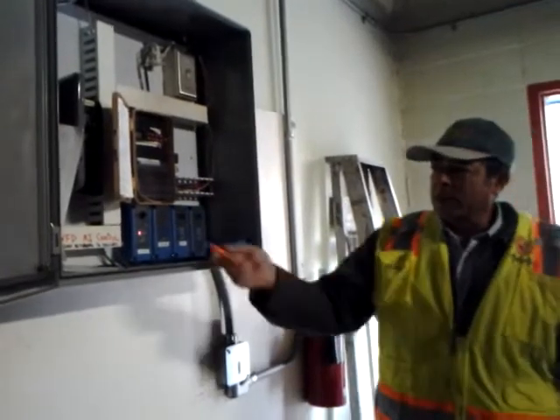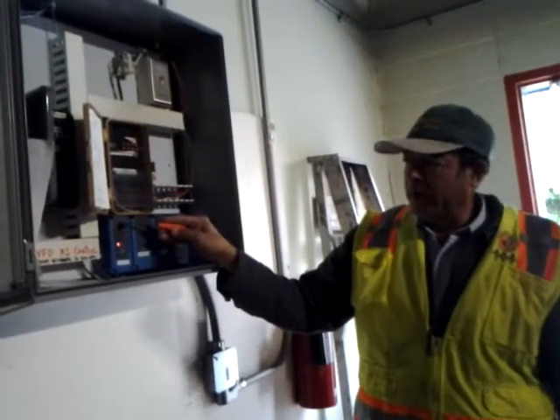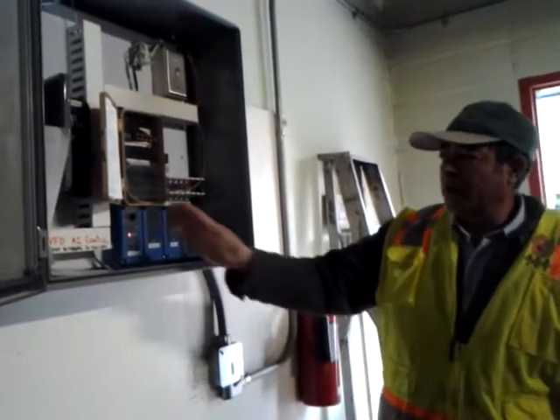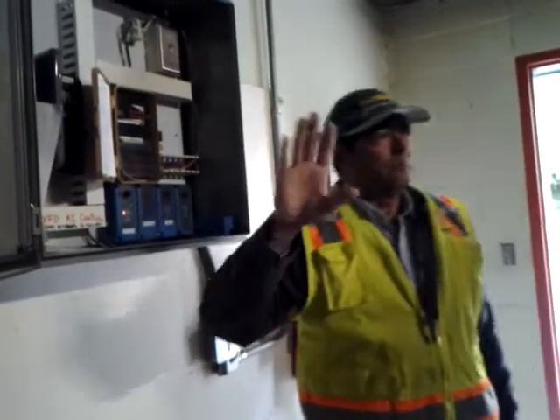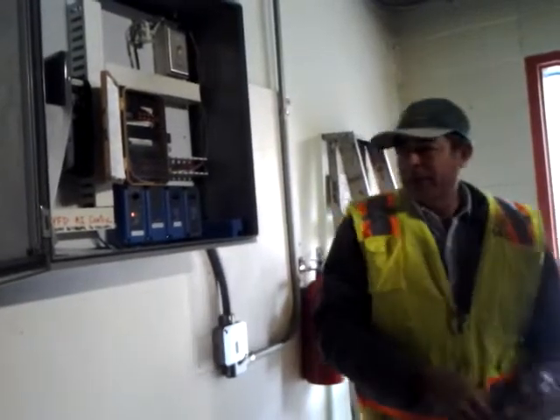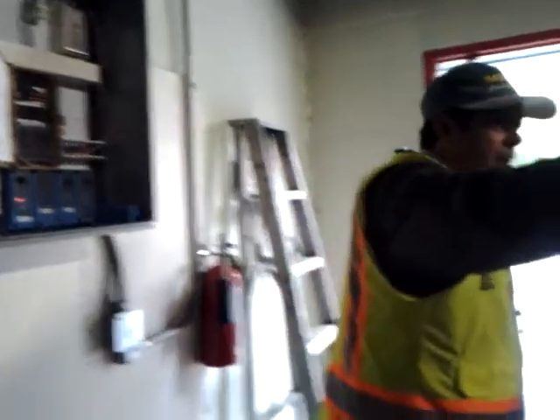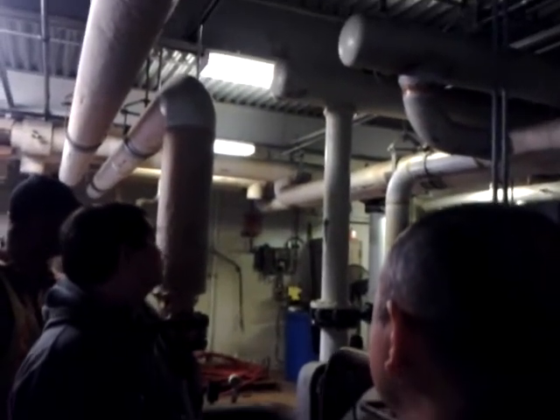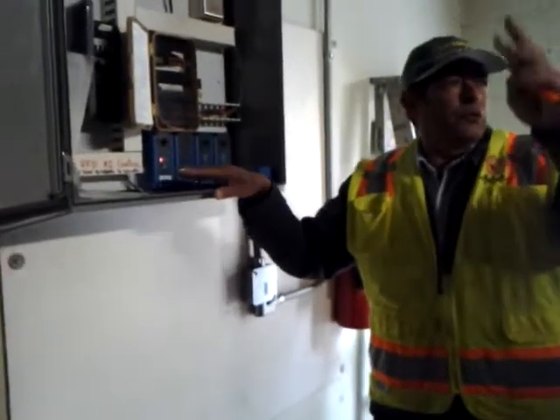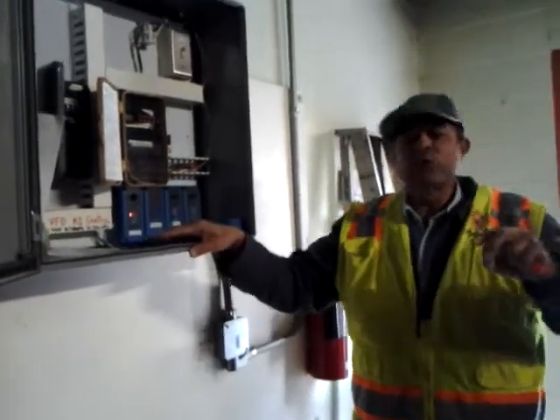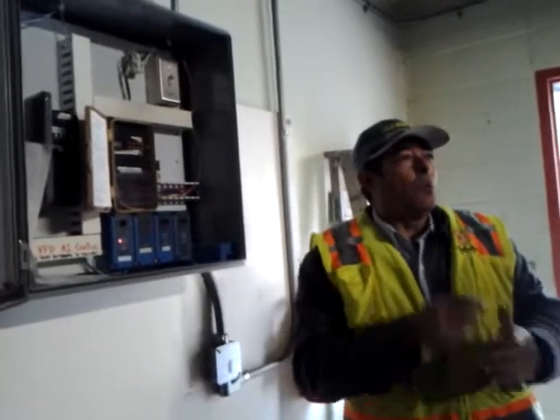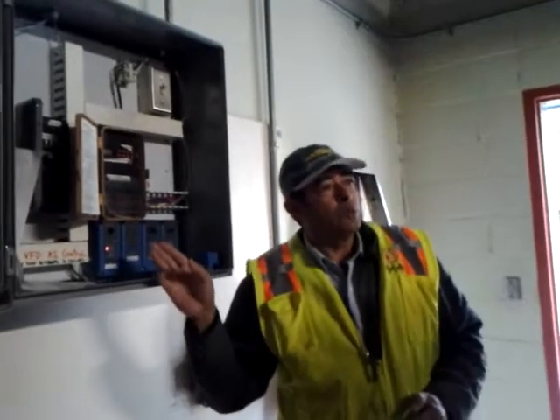It's not in here. But what this does is we tell them, okay, we want the water temperature at an X amount. So we said, okay, X amount, below that is 0, above that it's a little bit. Now, the sensor, you guys can see it, if you see that pipe with an arrow going up, if you see like a foot on the upper pipe, you'll see a little sensor in there with a wire. That sensor on the wire comes all the way down to here, and it is hooked up to here. So that is what a thermistor is. The transducer is for pressure. The thermistor will convert a temperature into an electrical impulse.